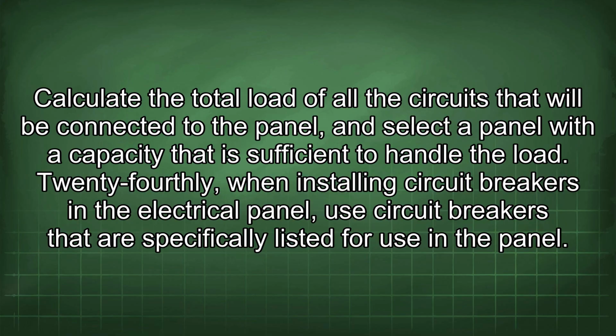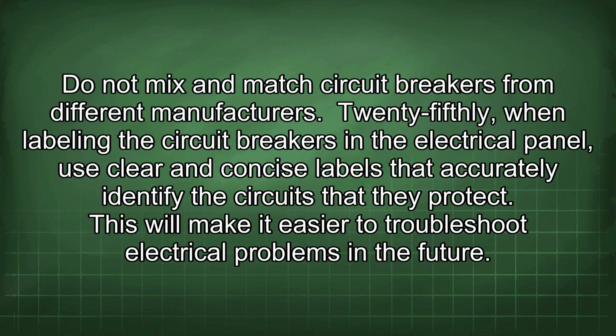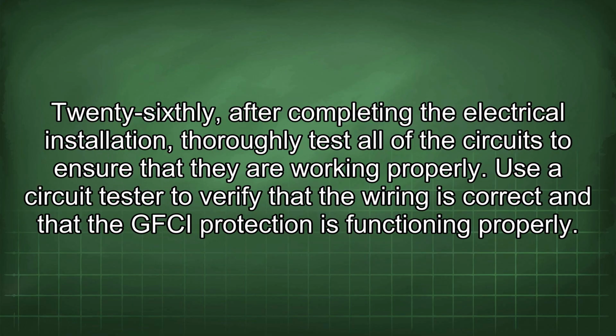24thly, when installing circuit breakers in the electrical panel, use circuit breakers that are specifically listed for use in the panel. Do not mix and match circuit breakers from different manufacturers. 25thly, when labeling the circuit breakers in the electrical panel, use clear and concise labels that accurately identify the circuits that they protect. This will make it easier to troubleshoot electrical problems in the future. 26thly, after completing the electrical installation, thoroughly test all of the circuits to ensure that they are working properly. Use a circuit tester to verify that the wiring is correct and that the GFCI protection is functioning properly.